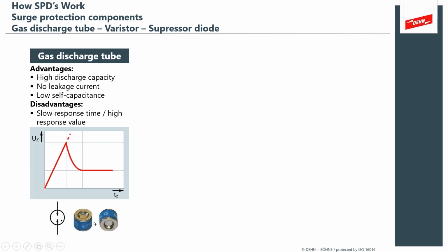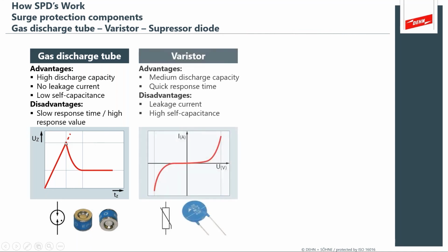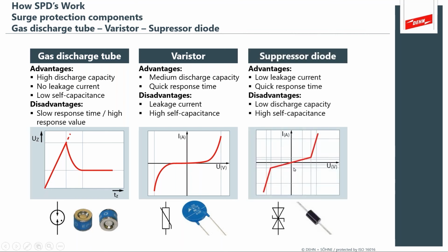DEHN manufactures very effective AC devices that work on this same principle, where the voltage reaches a high enough level and then it switches, voltage switching. This is in contrast to what are considered voltage limiting. And in this curve, you see that as the voltage rises, very little current flows, and then at what's considered the turn-on voltage, as you often hear it called. In a Zener diode, it's called the Zener voltage. Essentially what's happening is you get to a voltage limit, and then the device turns on and controls the voltage. In many applications, you hear the term clipping. In the audio industry, you hear distortion. Well, that's when the devices are clipping and causing nonlinear distortions in the signal.